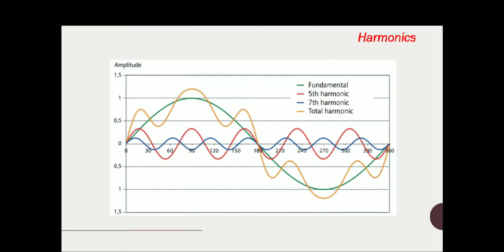Here you can see a pictorial representation of the harmonic. This green colored waveform is the fundamental waveform, the first order component at 50 hertz fundamental frequency. The first positive half cycle occurs during 0 to 180 degrees, and the negative half cycle is 180 to 360 degrees.